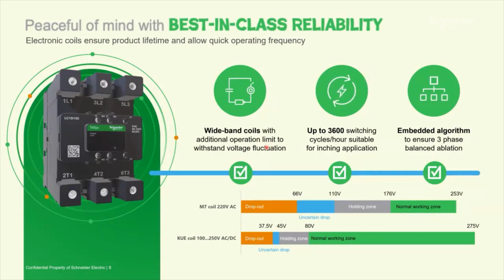So wideband coils give us a lot of advantages, and to show this, we have given a representation of two different coils down the line. You can see the first coil is the M7 coil with 220 volt AC, which comes with the existing Deca contactor, whereas the other coil is the KUE coil, which is with the new contactor. For the existing M7 coil for 220 volt, we can clearly see that the normal working zone is somewhere between 176 volt to 253 volt, whereas for the new contactors, the normal working zone is from 80 volt up to 275 volt.